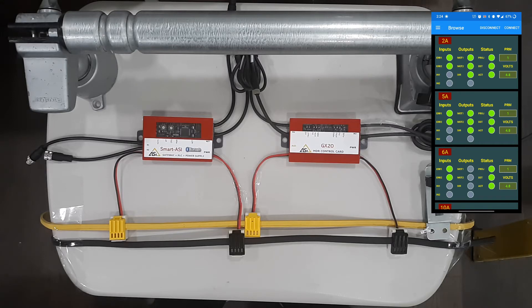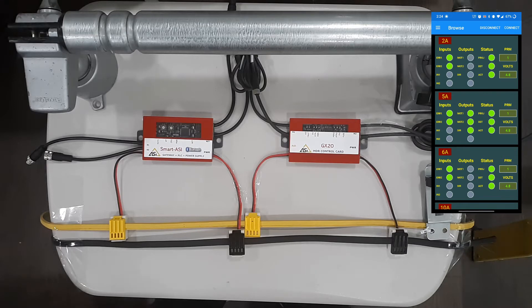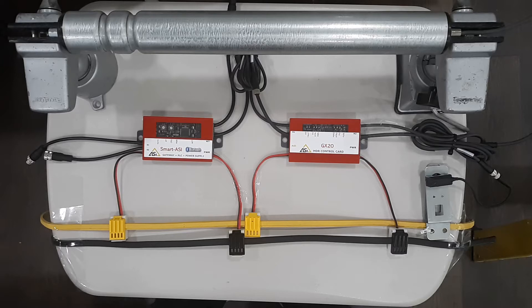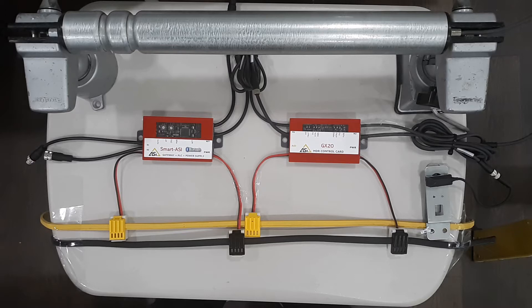You can turn on multiple outputs on AS-i slave devices to test conveyor sections even before the engineer has loaded the PLC program. The Smart AS-i Gateway also features a dual-port Ethernet switch that enables daisy chaining, and is used to connect to the PC as well as other PLCs using industrial protocols such as Ethernet IP, Modbus, and Profinet. The Gateway is accessible by these protocols with or without a PLC ladder program.